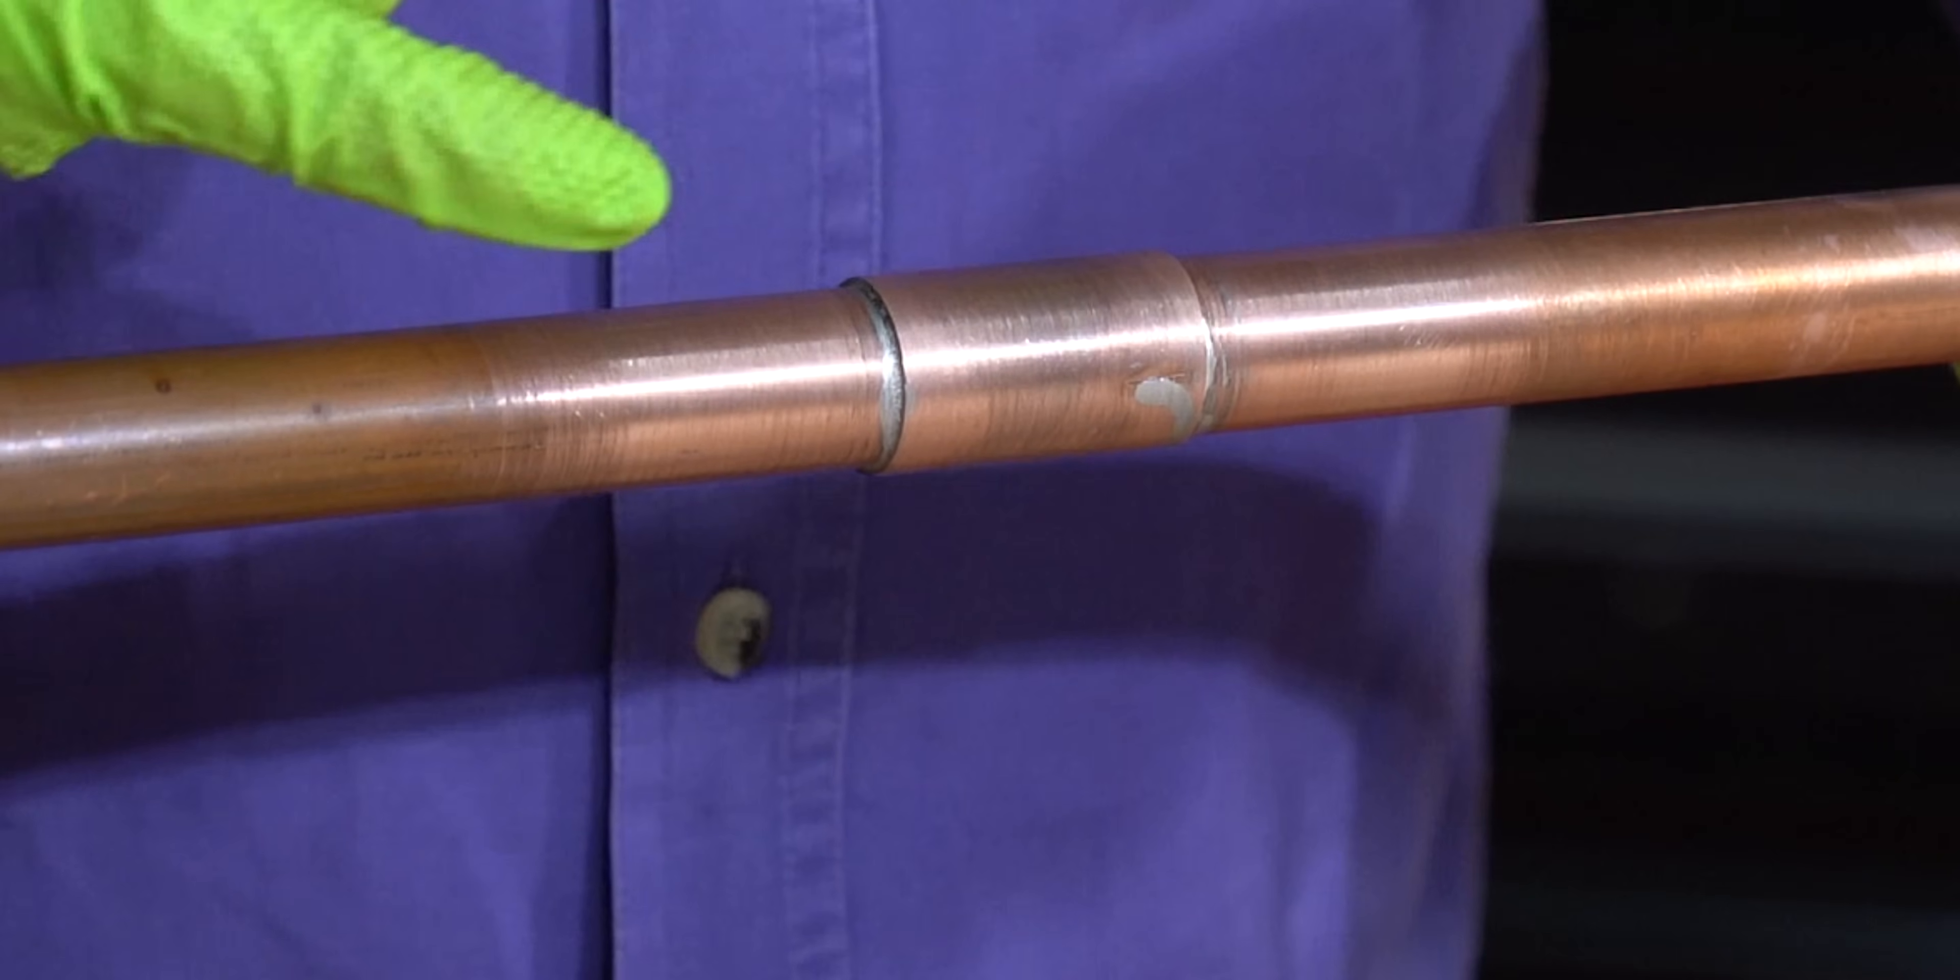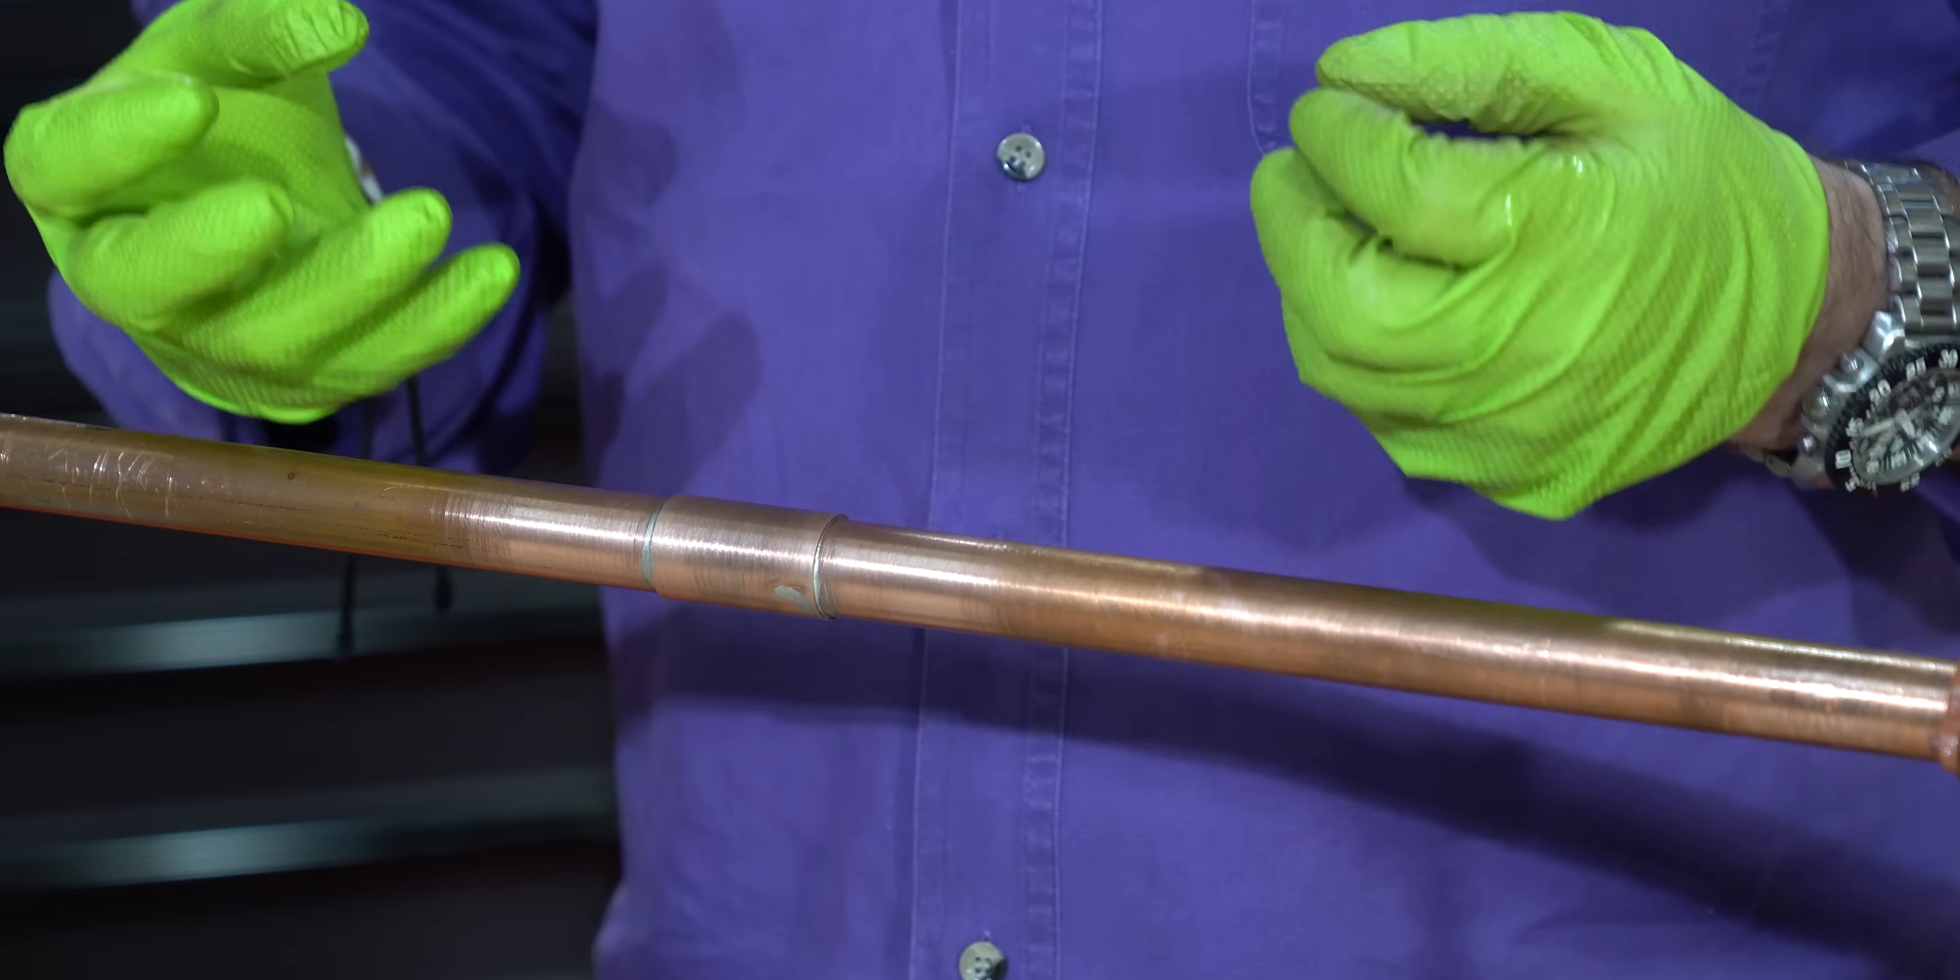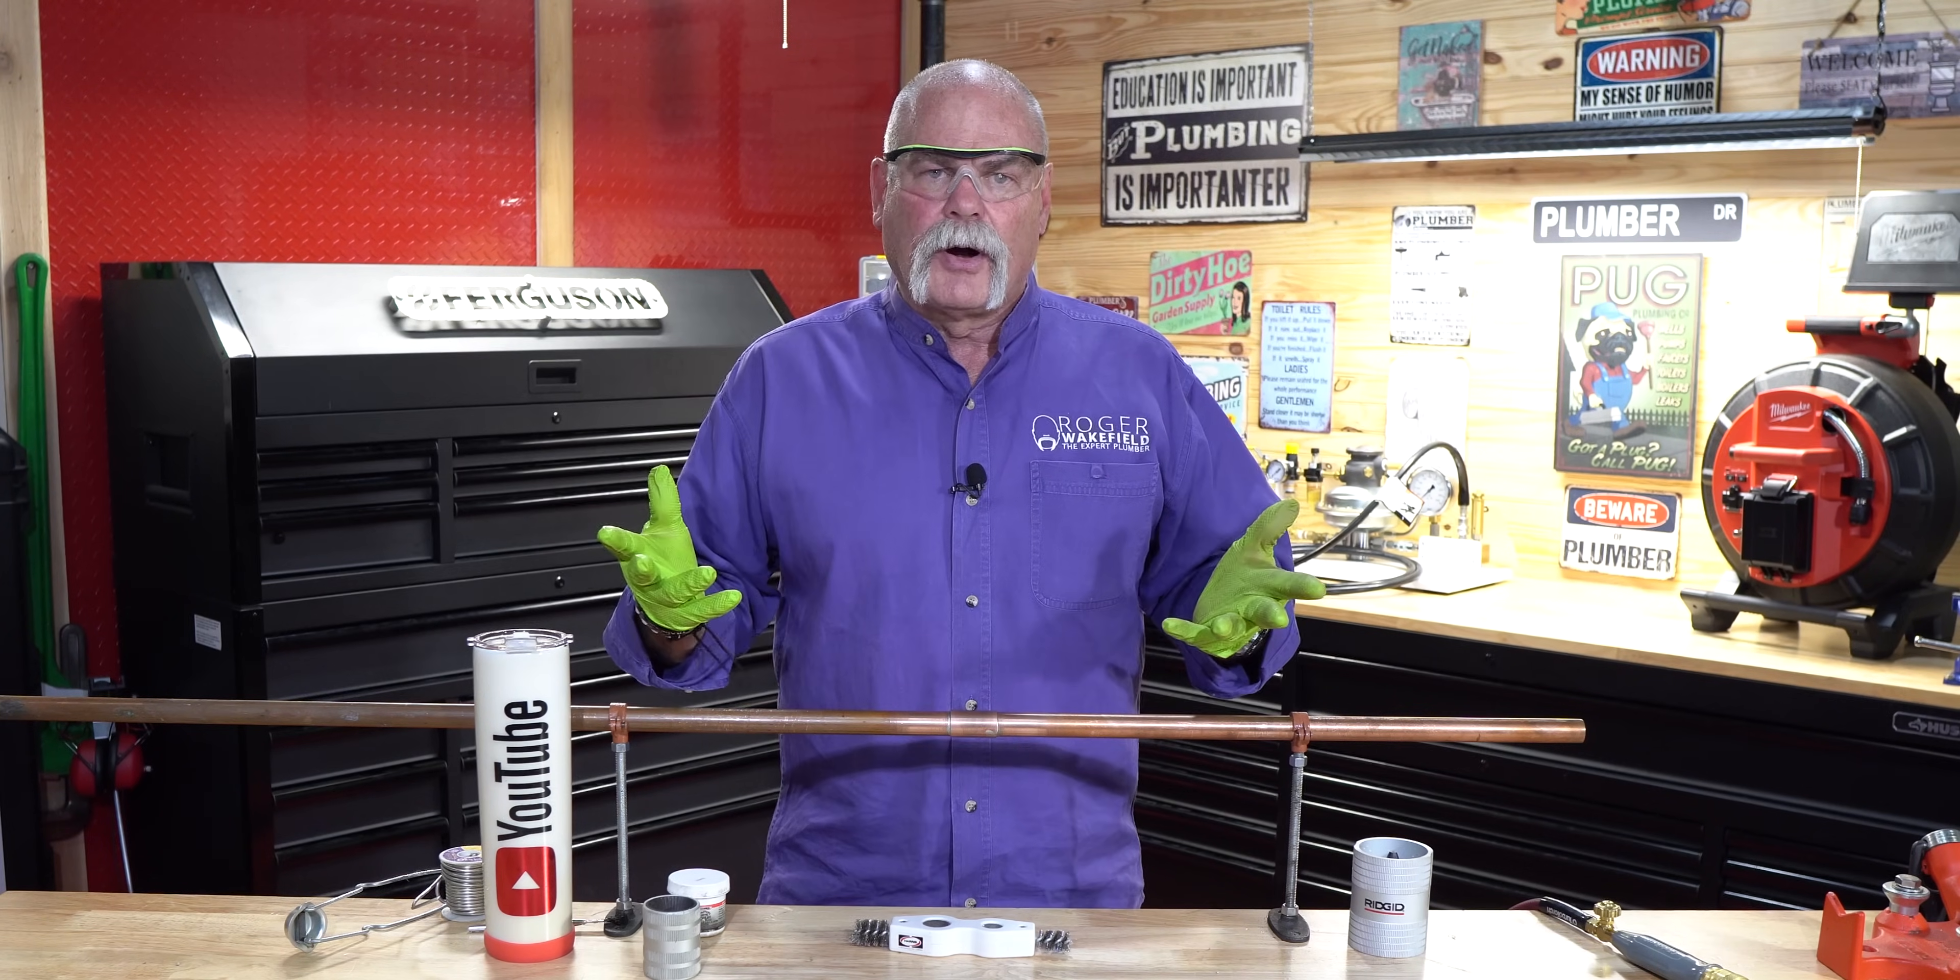So as you see, I cleaned it up a little bit, but making a solder joint takes a little bit of time. You've got to clean the outside of the pipe. You've got to clean the inside of the fittings. You have to bevel it. You have to ream it. It takes a little while to heat it up. Let your solder melt, go in there, fill the joint completely, and then let it cool down before you test it. So I completely understand why the next way I'm going to show you is understandable because it saves you labor. So let's cut this apart and get ready.